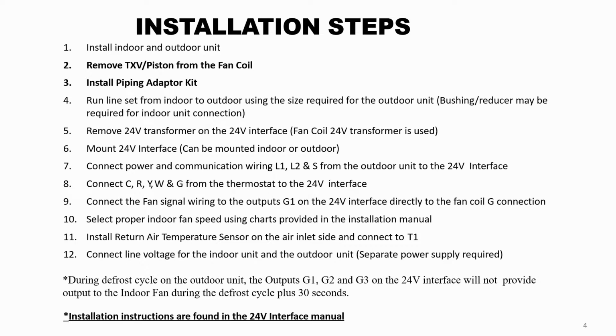Next, you'll need to select the proper indoor fan speed for the size unit that you have using the charts provided in the installation manual. After that, you'll install the return air temperature sensor on the inlet side of the fan coil. There is an extension cable if required if the interface kit is mounted outside. Next, you want to connect the line voltage for the indoor and outdoor unit, which uses a separate power supply.